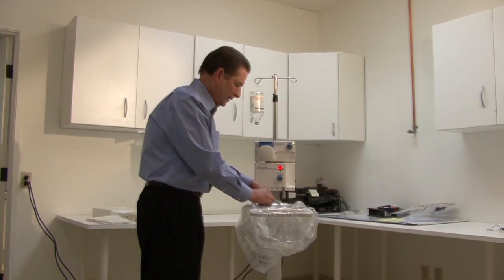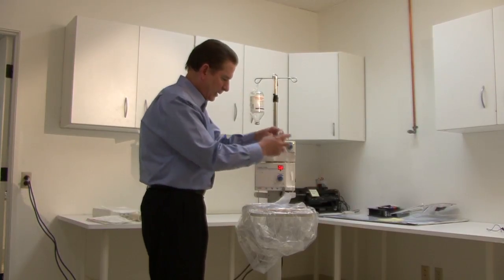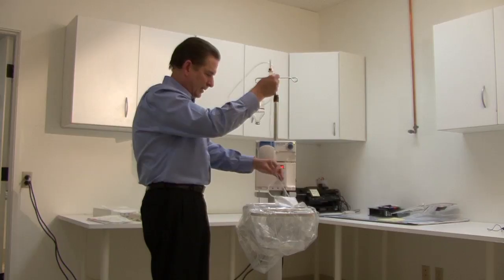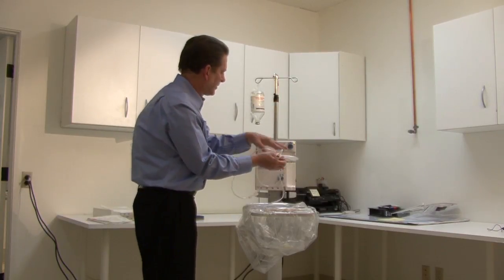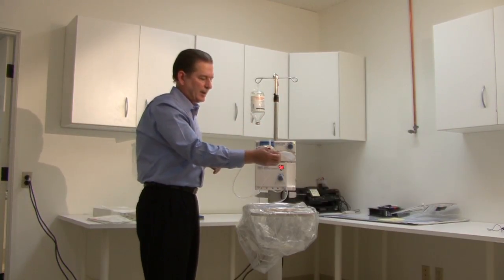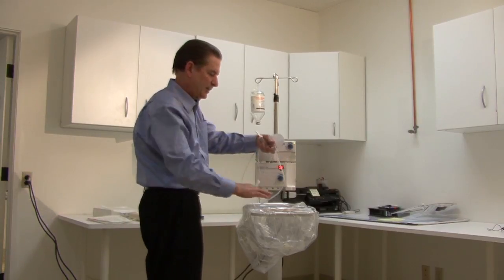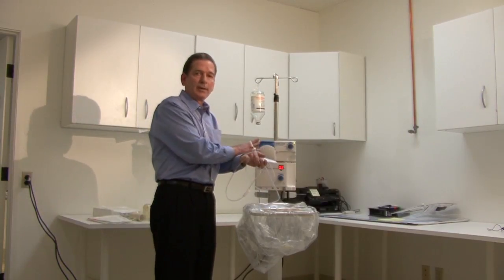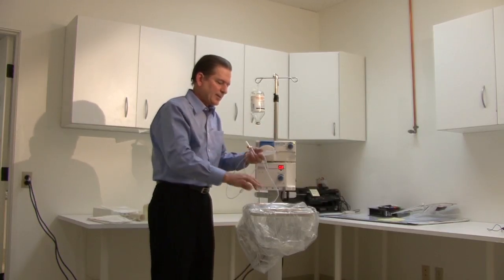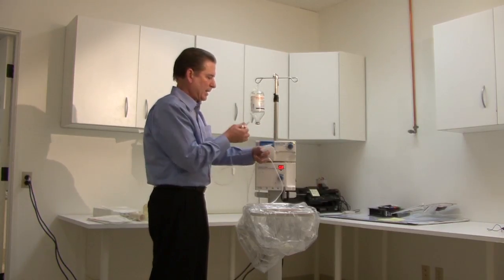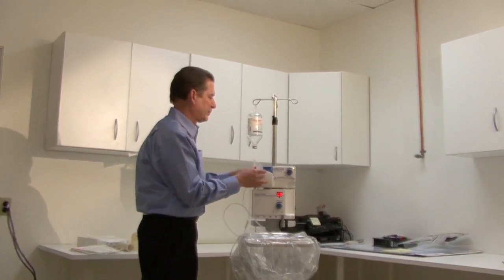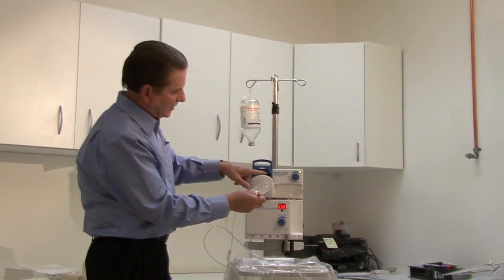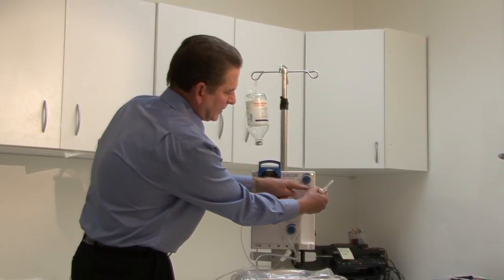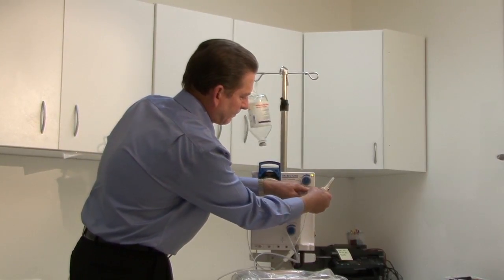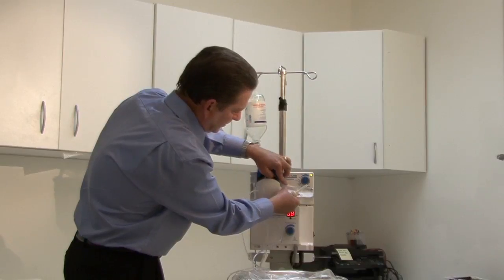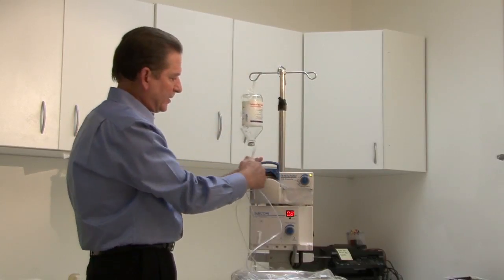But if we start with the bottle spike and we kind of go backwards, we'll get to the little collection bag. These are the items that are going to be mounted onto the irrigation aspiration pump. So whoever's scrubbed in can hand this off to whoever's circulating so that they can go ahead and set up the pump. So we'll keep as much of this on the sterile field. And to set up the pump is really pretty simple. There's a simple roller pump for aspiration. The little collection bag just goes on these little pins. And we just want to put the bag on so that the pump tube is heading toward the pump.